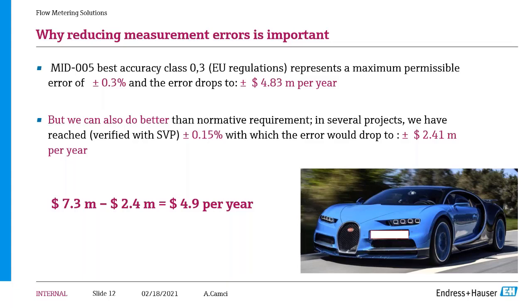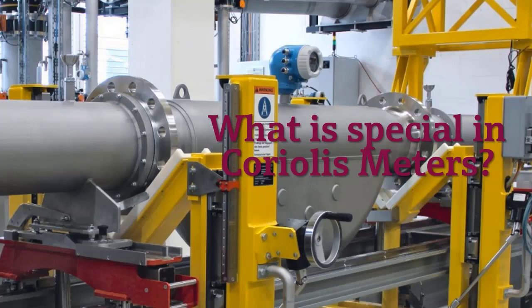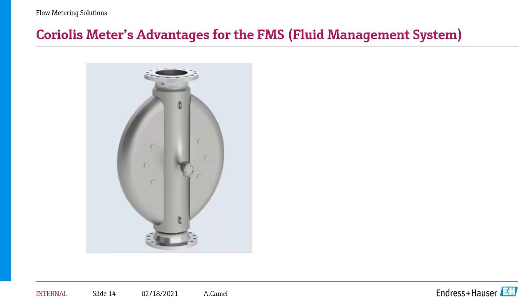For reducing the measurement errors, the Endress+Hauser product is the Coriolis meter. And what is special in the Coriolis meters? What are their advantages? On the left-hand side, you see a Promass X, the biggest available Coriolis meter in the market. The advantage is that this meter does not need pressure and temperature compensation. It is direct mass metering, and the final amount is not affected by the pressure changes or by the temperature changes.